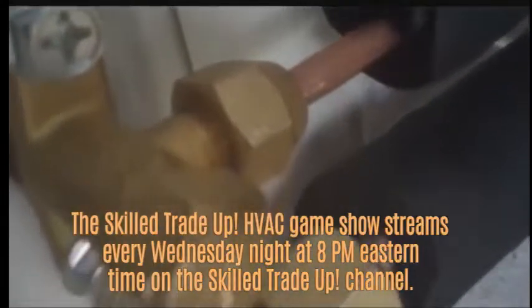Alright, we're putting on some flares here. What I do is put some thread sealant on these. This is Nylog thread sealant, and it holds up under high pressure. If they're starting to leak or something like that, it's able to counteract that leak, and it does a really good job of sealing flares. I've had a small leak on flares at about 350 pounds, leaking a pound every so often, and this stops it dead in its tracks. It's just awesome. There are blue ones for HFC and red ones for CFC and HCFC refrigerants. It's really good.